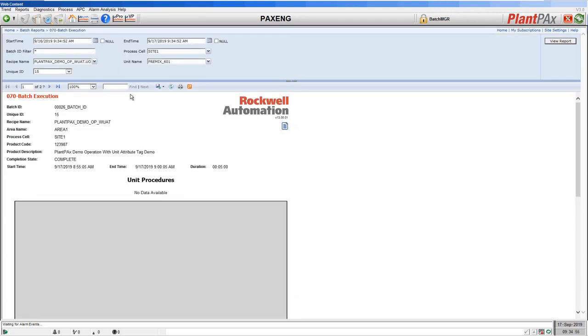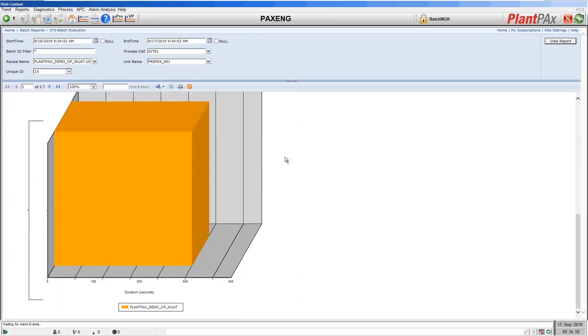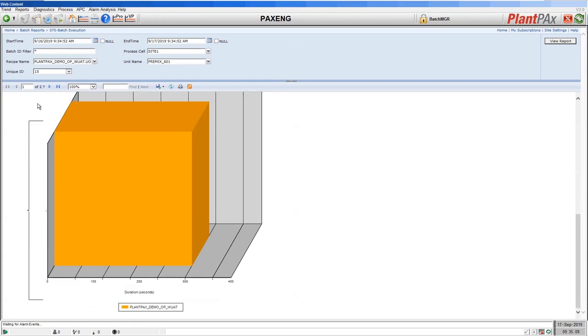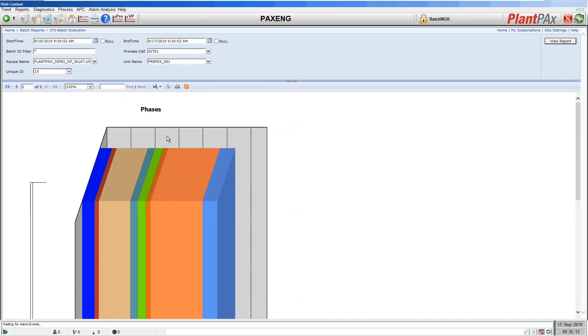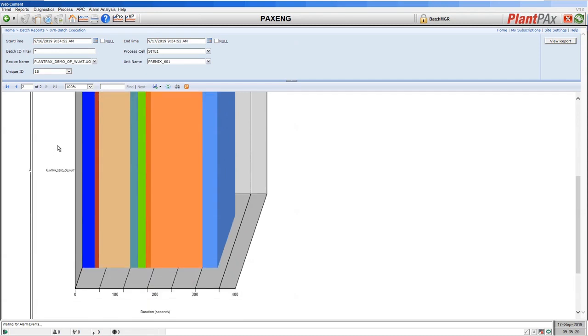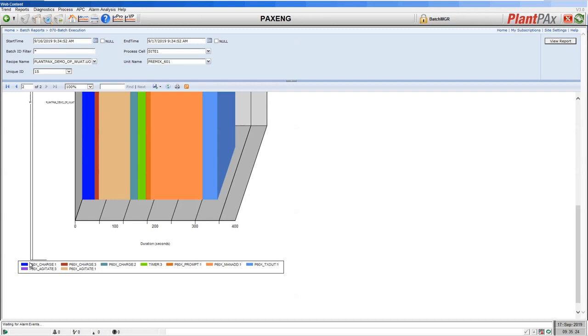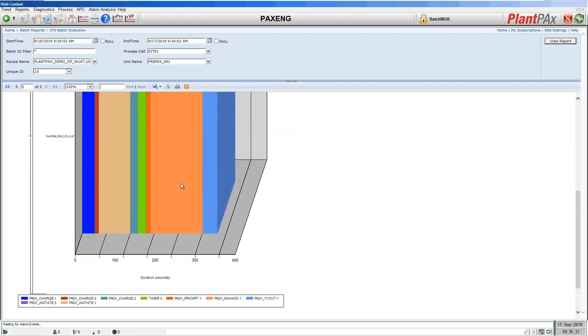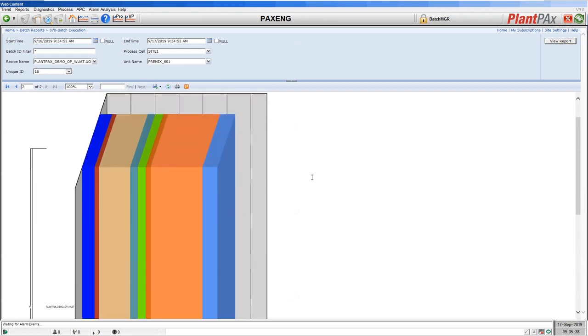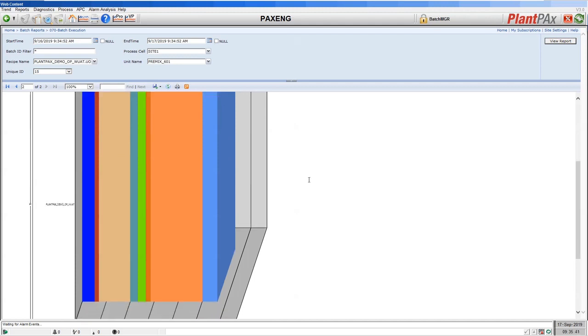The next report is batch execution. This is about the timing of the batch. Our batch just had one operation. In S88, your recipes can be split into different levels, and we ran a basic recipe that just had a single operation. On the second page we can see each of those equipment phases — the processing steps — and how long they ran. You can see where the time is being used. Here we can see that the manual addition was the stage in our recipe that took longest. You can use this to try and improve how fast you can make recipes by seeing where the time is being used.